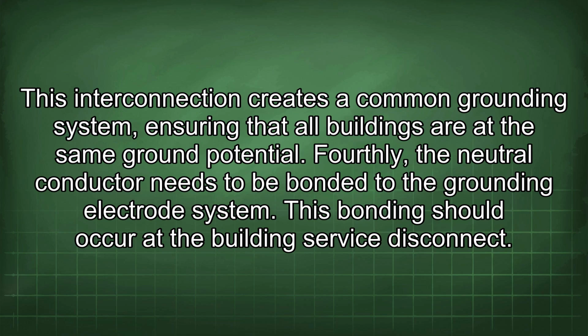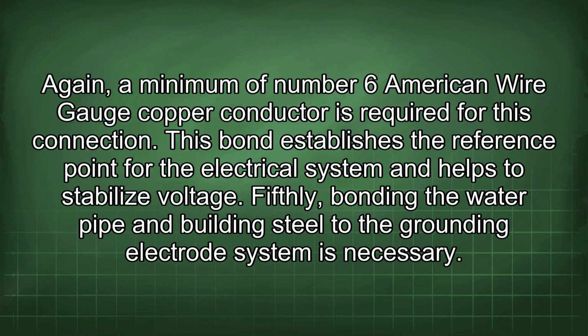Fourthly, the neutral conductor needs to be bonded to the grounding electrode system. This bonding should occur at the building service disconnect. Again, a minimum of number 6 American wire gauge copper conductor is required for this connection. This bond establishes the reference point for the electrical system and helps to stabilize voltage.